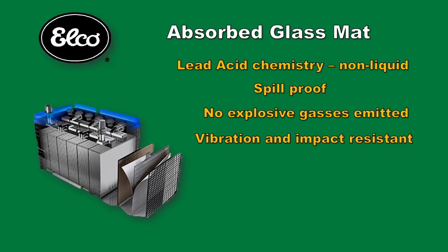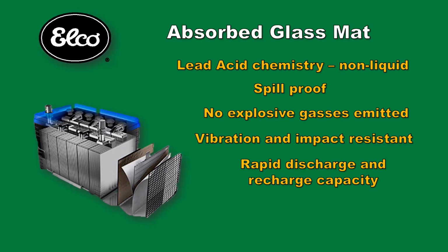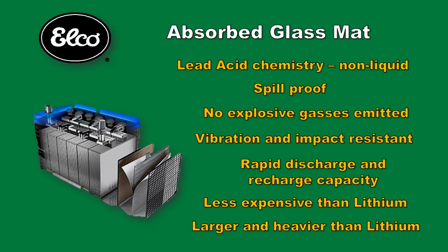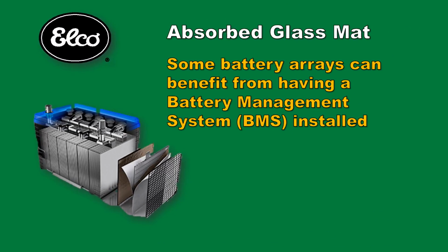They are vibration and impact resistant to damage, can be rapidly discharged, and have high charge acceptance rates. They are more expensive than flooded wet cell batteries, but less expensive than lithium. They are also larger and weigh more for any given amp-hour capacity rating compared to lithium types. While not required, AGM battery arrays can benefit from battery management systems, or BMS for short. A BMS keeps the batteries and cells balanced for a longer battery life.